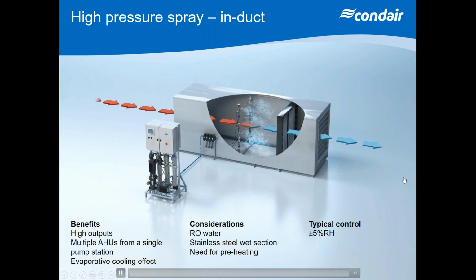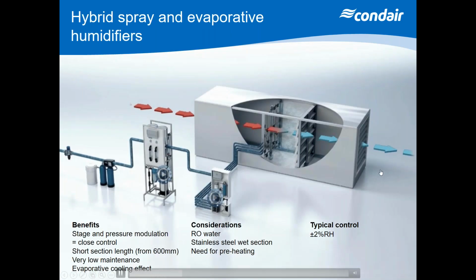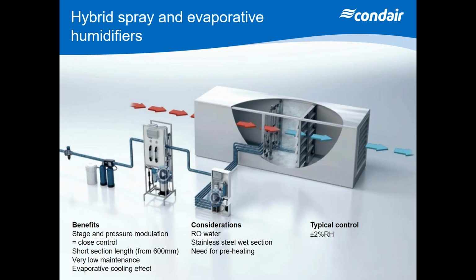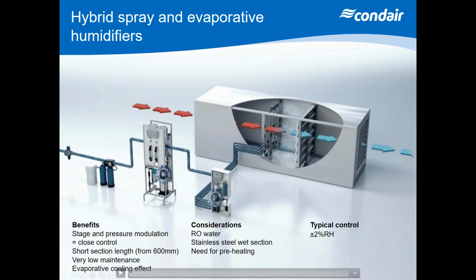If I want to do better than that, I can utilize both types of technology with a hybrid system. Well, a hybrid system is going to take mains water, it's going to run it through a softener and a reverse osmosis plant, and a silver ion exchange, and we're going to take that water to a nozzle array, where we've got many, many more nozzles spread across the whole cross-section of the AHU. And I can turn off sections of these nozzles to give me many more stages of control. And I can have up to 31 stages of control from systems such as this. So it will give me plus or minus 2%.